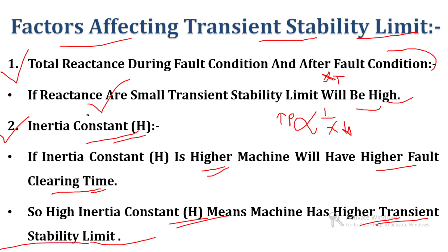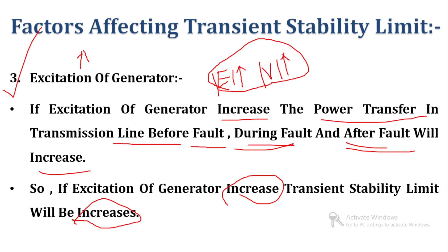Now third one is excitation of generator. If excitation increases, then the generated EMF will increase, and due to that terminal voltage will also increase. So if excitation of generator increases, then power transfer in transmission line before fault, during fault and after fault will increase, because the increment in excitation will increase the terminal voltage and generated EMF of the alternator. So it will increase the power transfer capability of the system. So if excitation of generator increases, transient stability limit will also increase. That is the third factor affecting transient stability limit.